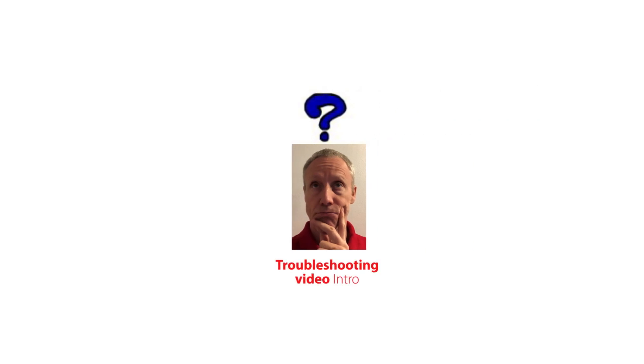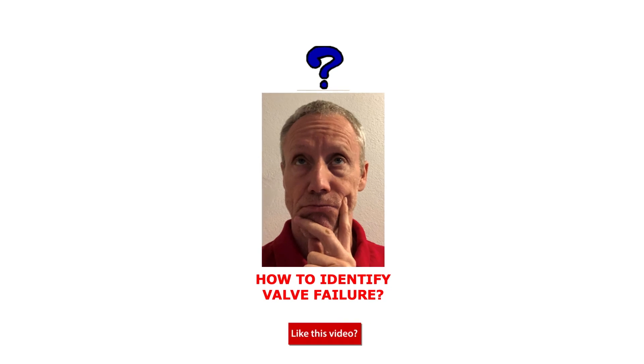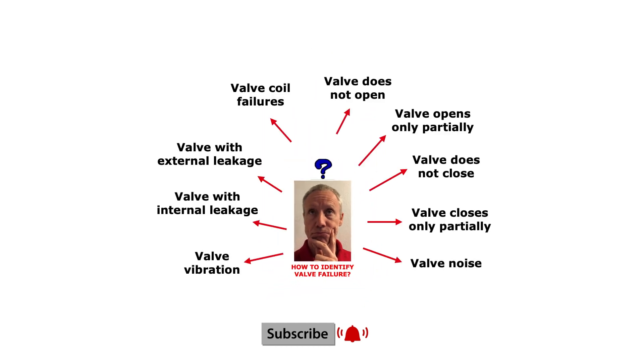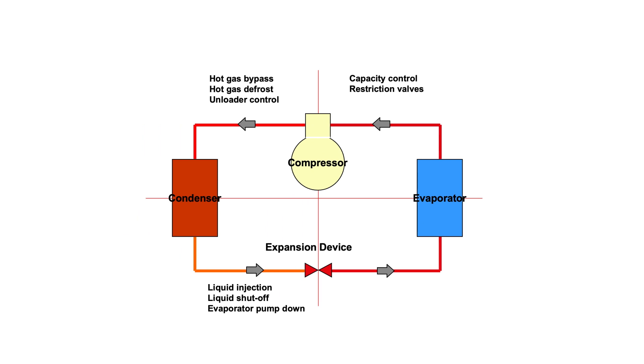This video gives you troubleshooting tips related to how to identify possible solenoid valve failures in a refrigeration system depending on valve location and valve function. How do we efficiently identify possible solenoid valve failures? Here you see the potential solenoid valve failures which might happen in the refrigeration system: valve noise and vibration, valve does not open or opens only partially, valve does not close or closes only partially, valve internal or external leakage, and valve coil failures. These valve failures might affect the refrigeration system in different ways depending on the valve location and function in the system.